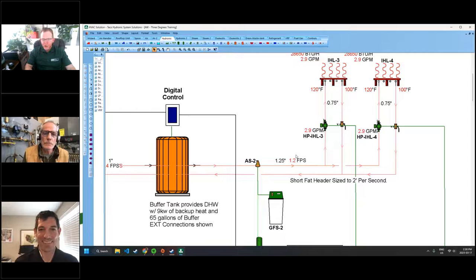Okay. So in this particular scenario, where I've highlighted, hopefully that shows clearly, we want to make sure that flow velocity is very low. Typically in a system like this, we want to make sure we have turbulence so we get good heat transfer. So we want to be like 2 feet per second. Here, we want to drop that flow velocity below 2 feet per second so that this pump and this pump physically will not see each other or hydraulically compete with each other. The other nice part is if we drop this below 2 feet per second, we're going to have laminar flow inside of that piping, and that's actually good. It means there won't be as much heat transfer on that piping. So if it's copper, we don't have to worry about a radiator in the mechanical room.